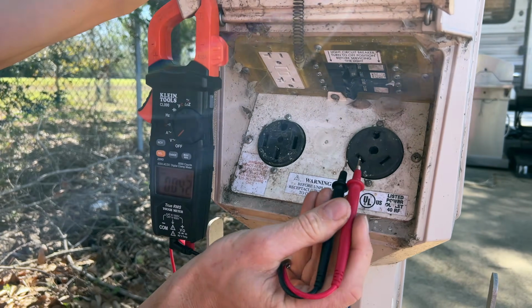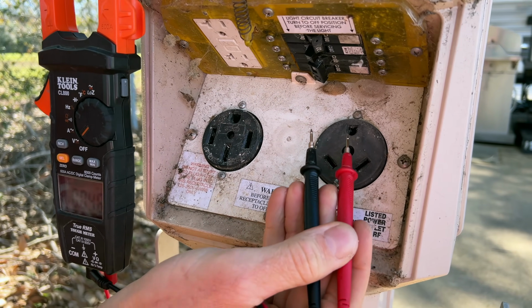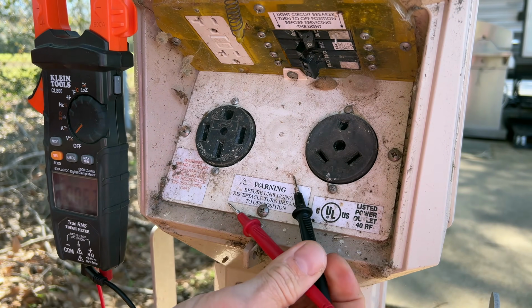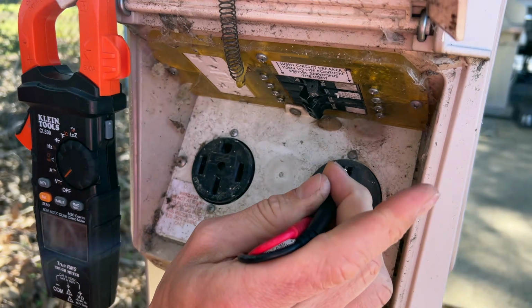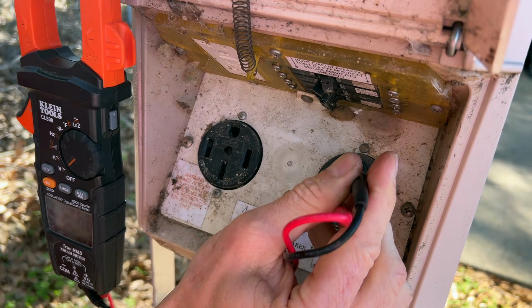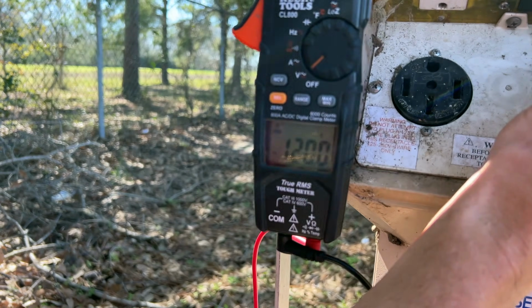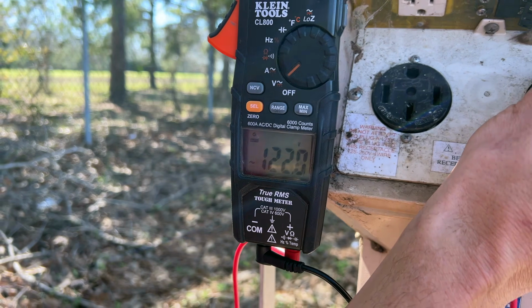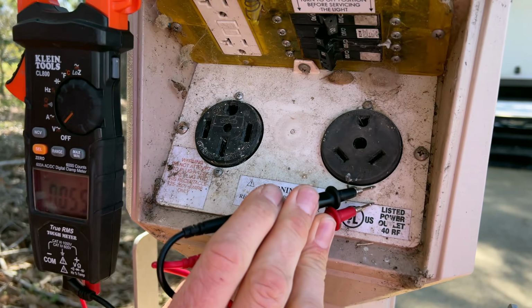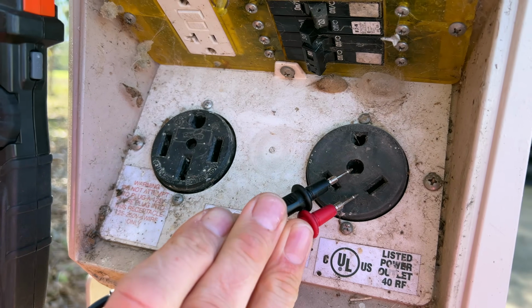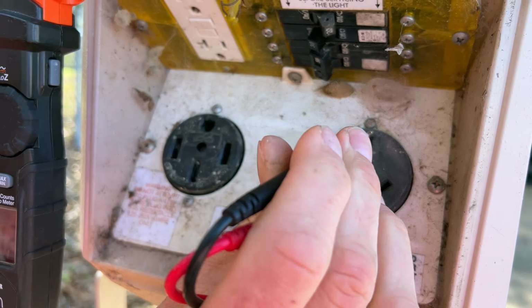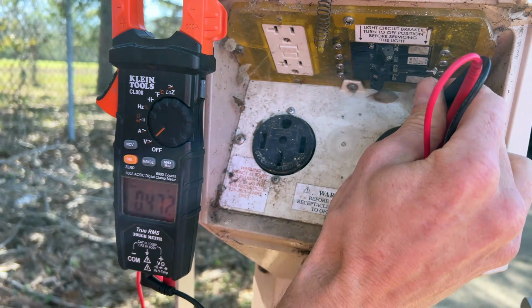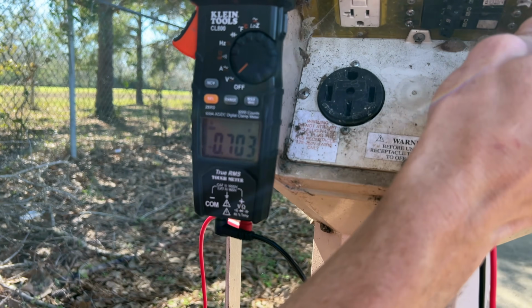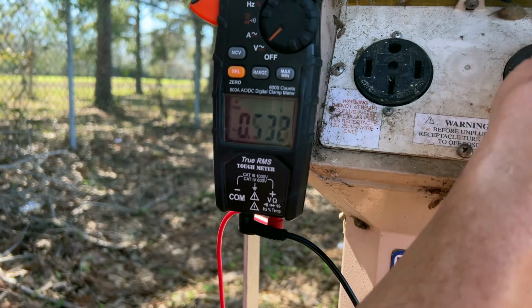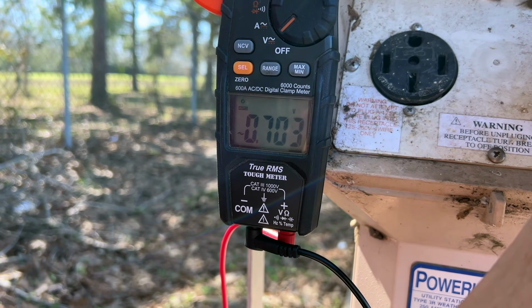Now I'll check from the hot bottom left to the ground in the top. So again, I'll put my red lead in hot, my black lead to ground. Should be around 120 volts, just like the neutral. So the next check to test on here is from neutral in the bottom right to ground in the top. This should be 0 or pretty close to 0. So that is good. So we're right around 0, that's good.